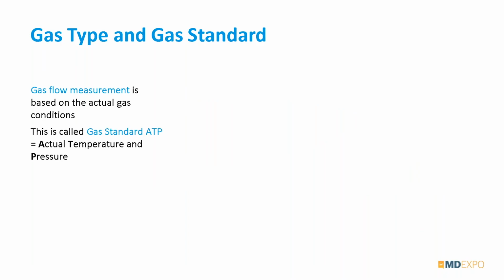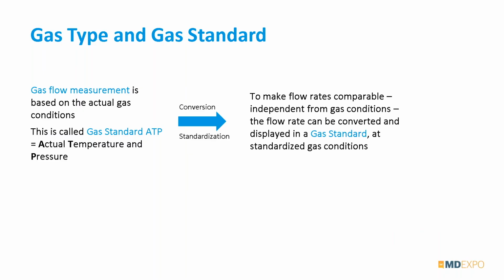So when we use gas flow measurement, we're actually measuring the live actual conditions and characteristics of gas. And we can call that a gas standard called ATP, or actual temperature and pressure. There are many different gas standards used in our industry, and we can apply those gas standards to this measurement and display them in something else. So we can actually take our mass flow measurement and add an offset to it and display it in a different gas standard.